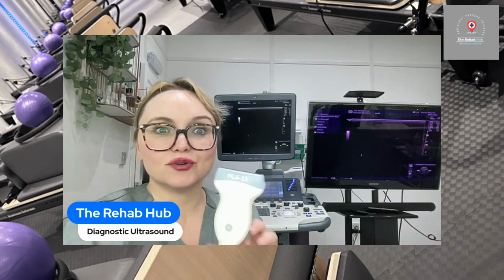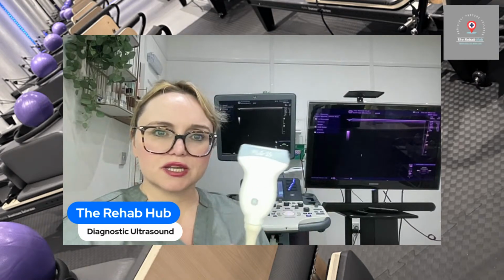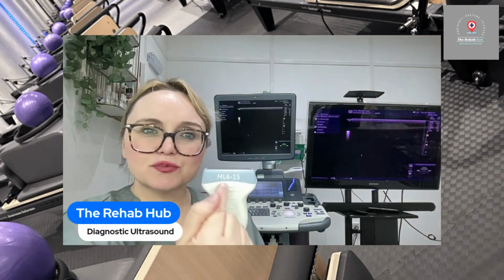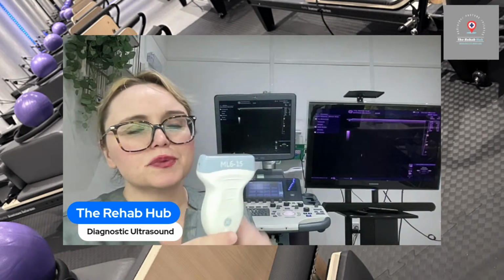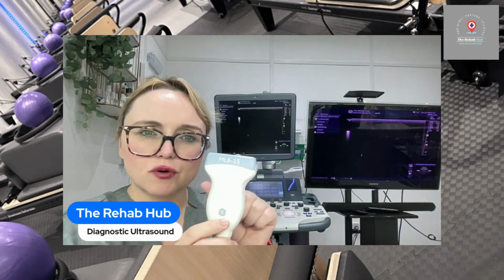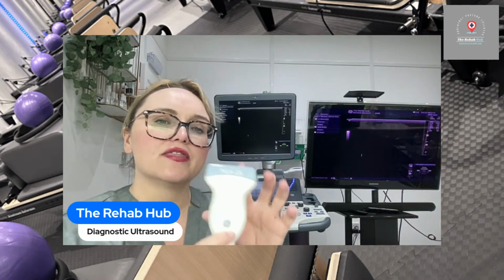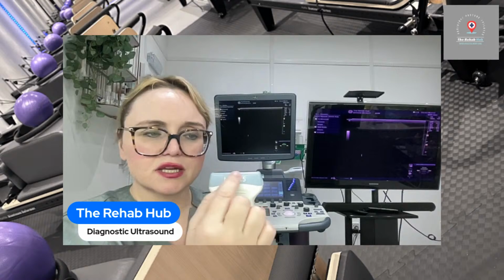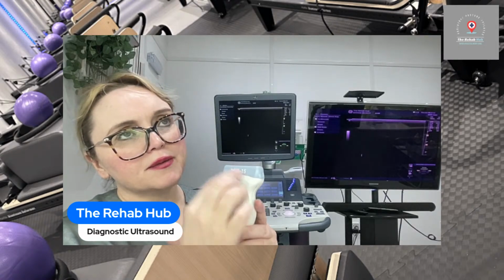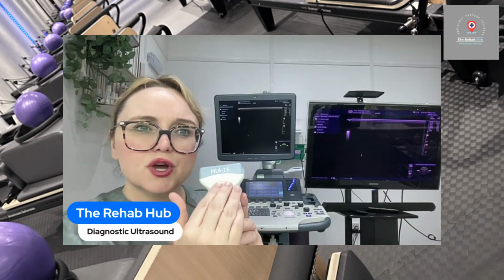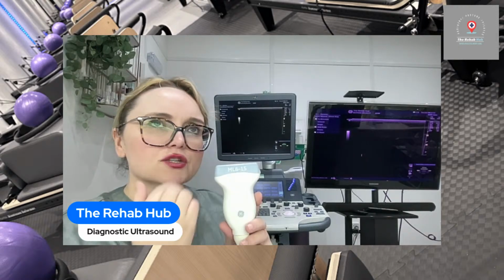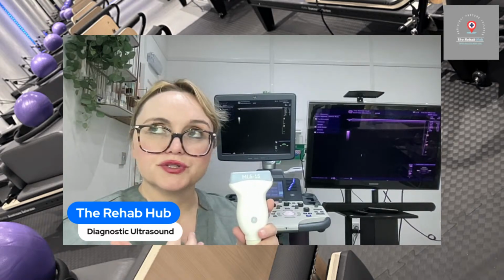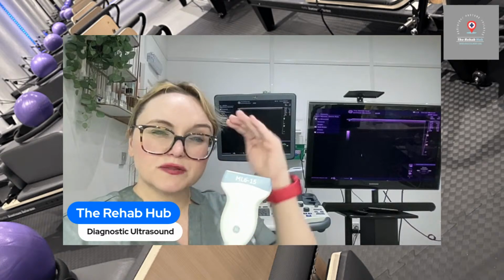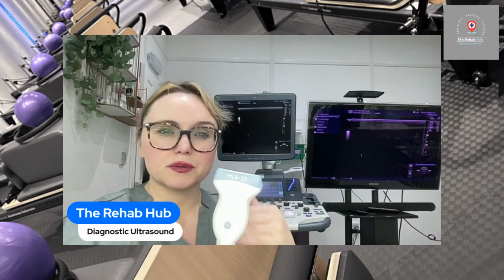Musculoskeletal would be stuff to do with ligaments, tendons, bones, bursa, these kind of things, not livers or any of those kind of things. But it's the same machine. Just this will look different. So this is what's called a linear probe, and this is primarily for musculoskeletal things. And that's because of the frequency that this can go to. When we look at things that are much more superficial, we need to have what's called a higher frequency so that we can get a better image of those structures that we're trying to look at. Whereas if we're looking at deeper tissues, we need to have a lower frequency.